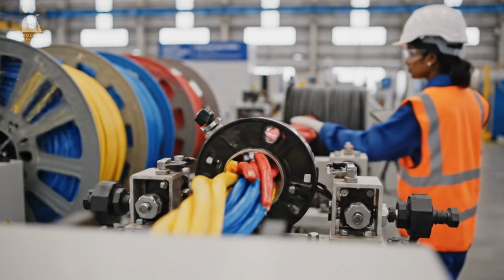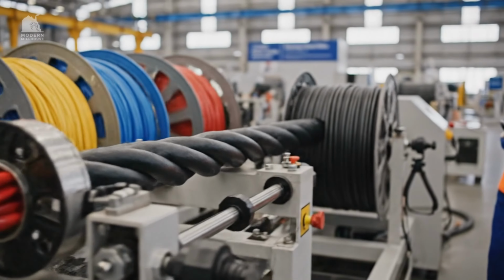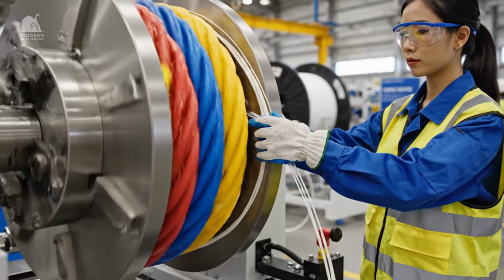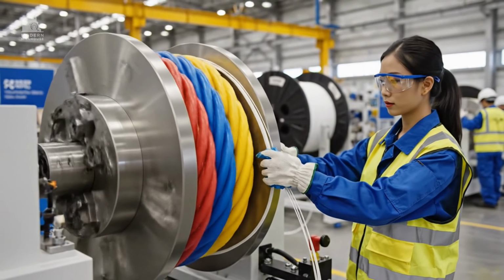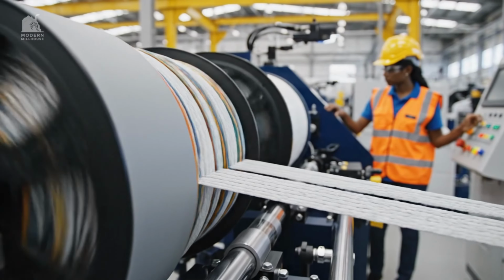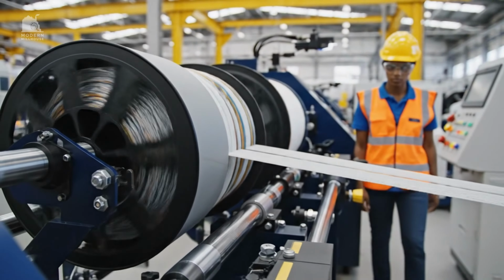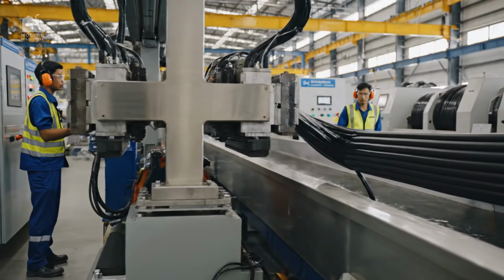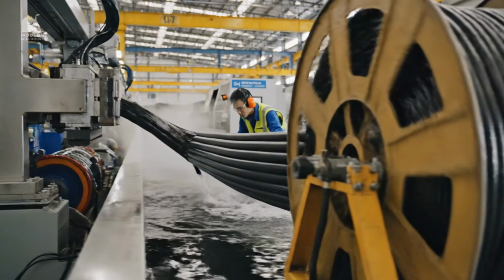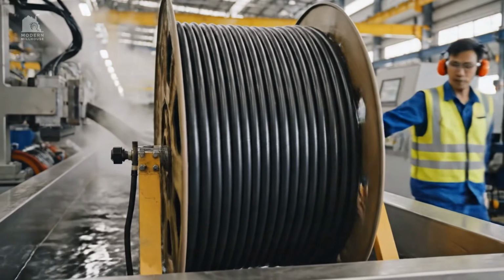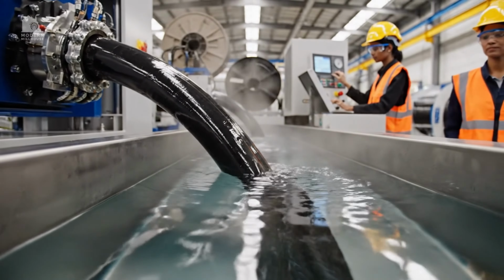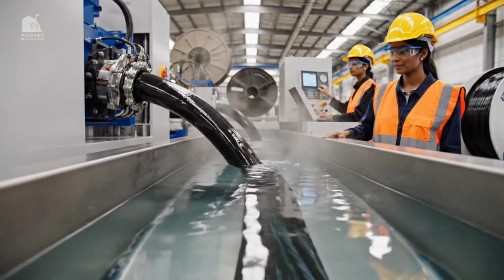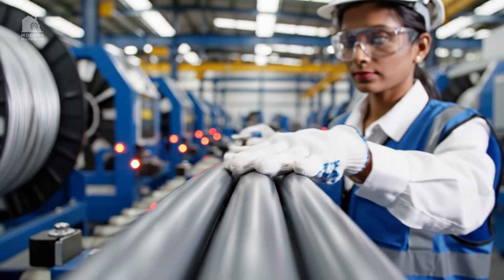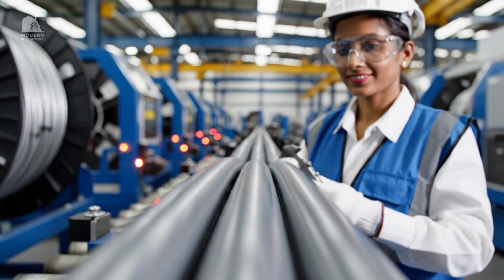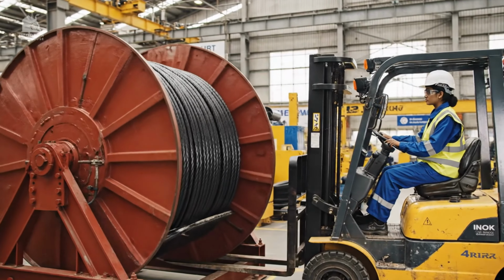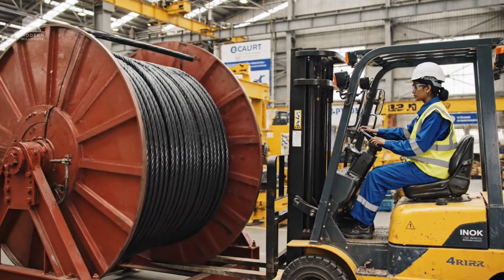To build a cable, several insulated conductors are twisted together into one stable assembly. Cabling forms geometry, keeping cores evenly spaced while fillers maintain a round outer shape. Binding tape holds the assembly tight so it won't open up when the outer jacket is applied. An outer sheath adds abrasion resistance and protection from moisture and handling damage. Just like insulation, the jacket is cooled carefully to prevent dents and preserve smoothness. A clean jacket surface is more than cosmetic. It reduces crack initiation and improves durability. The finished cable is wound onto large drums designed to protect the jacket during transport.